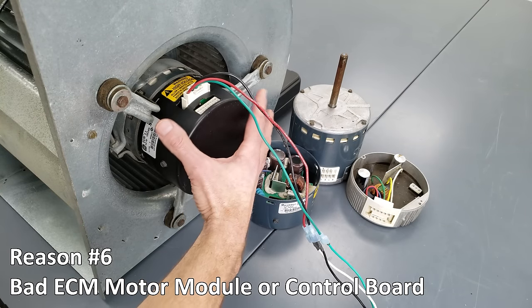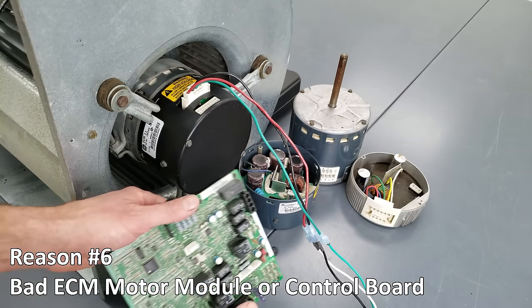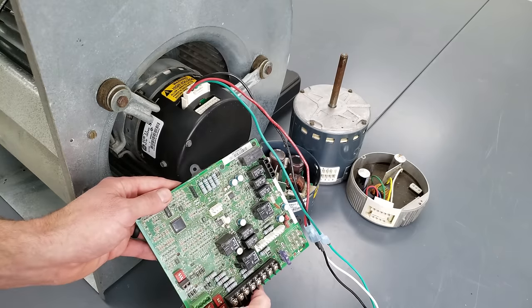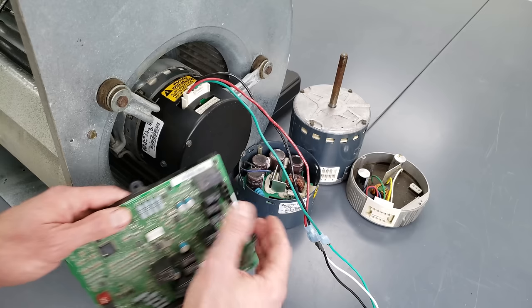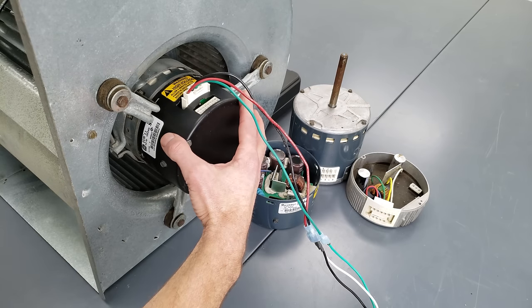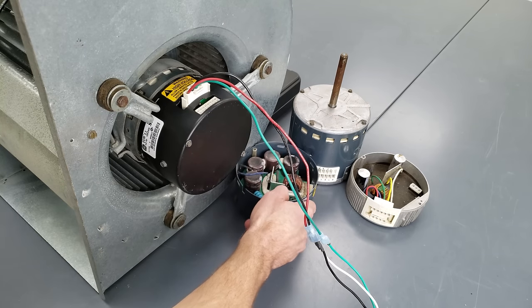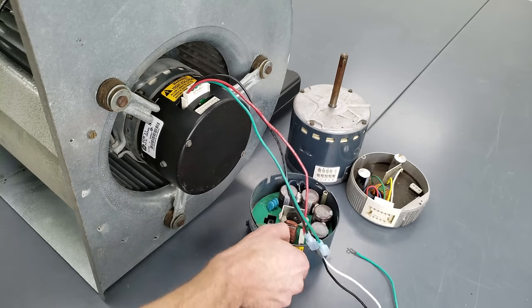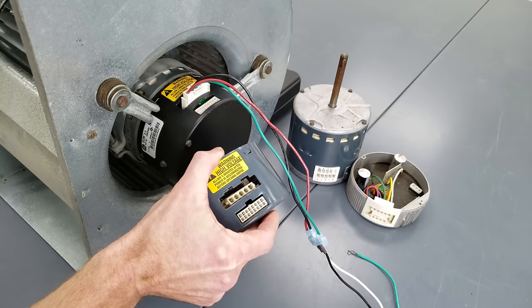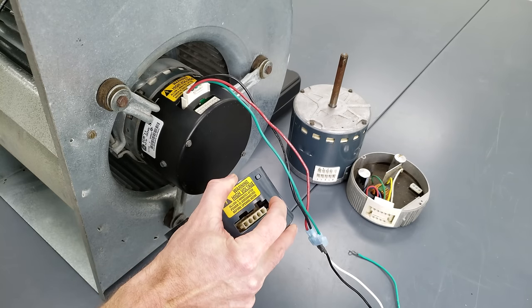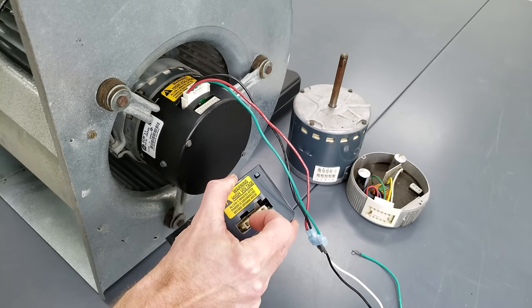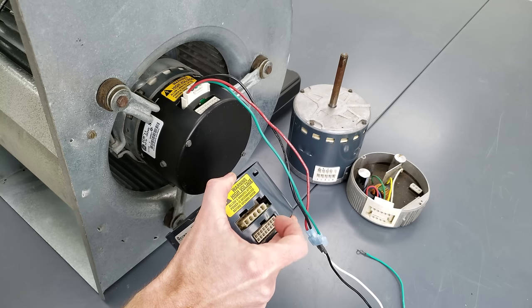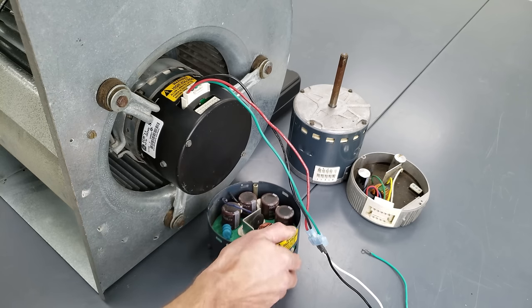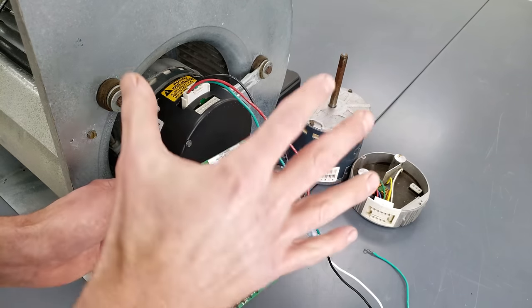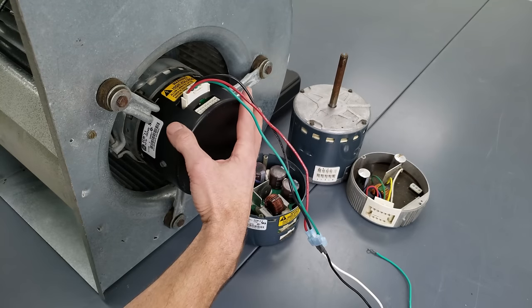Problem number six is when you have an ECM blower motor that doesn't turn off, and that could just be due to this hub or module assembly here, or it could be due to the control board. Some furnaces are equipped with ECM blower motors. In this case, it's a 2.3, and the 2.3 has a 16-pin connector right here. These have power all the time, high voltage power, but the signal down here for the blower motor to turn on is communicated between the control board and the module itself.